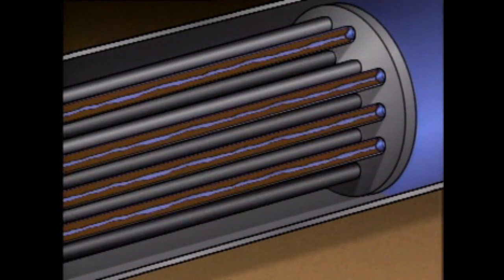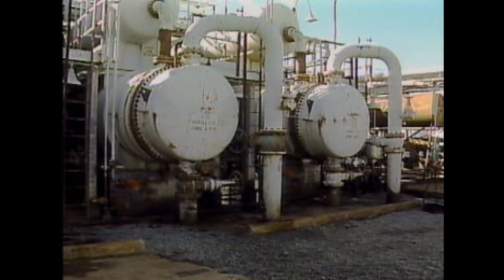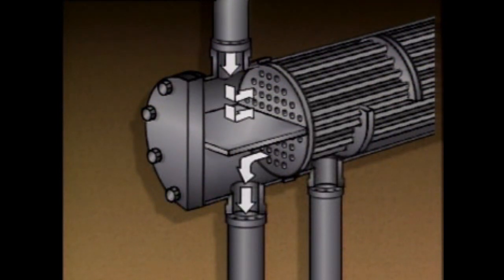One way that heat exchangers can be cleaned is by using chemicals. When this is done, a chemical solution is passed through the heat exchanger to dissolve the fouling on the walls of the tubes. Fouling on tube walls can also be removed by scraping or by spraying with high-pressure water or steam. However, these methods require the heat exchanger to be shut down and taken apart. In some heat exchangers, cleaning can be accomplished using a technique called backwashing, which is the reversing of flow through the heat exchanger. This technique is effective in temporarily dislodging materials from the ends of the tubes and the tube sheets.